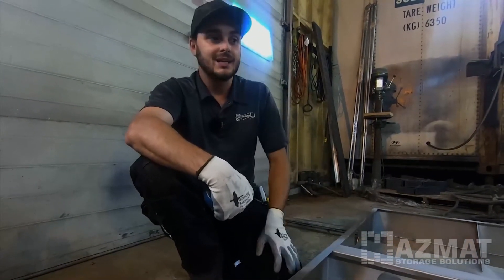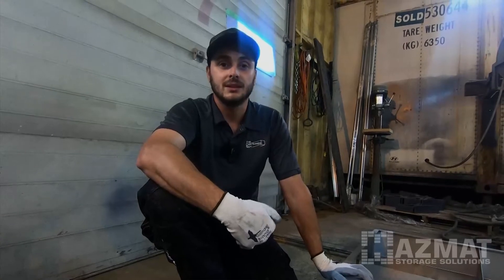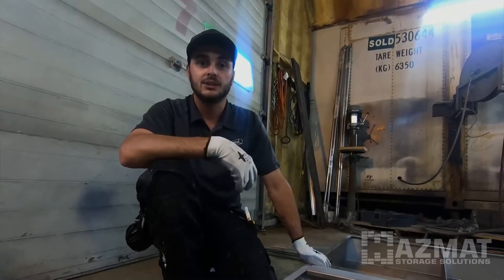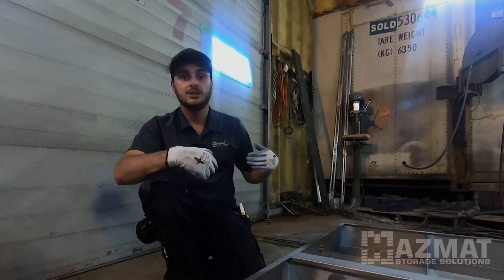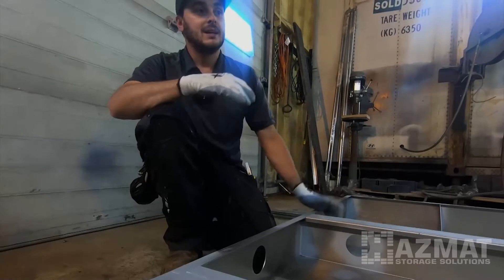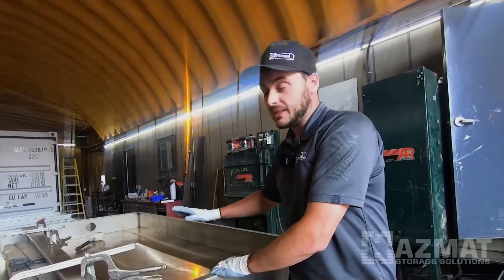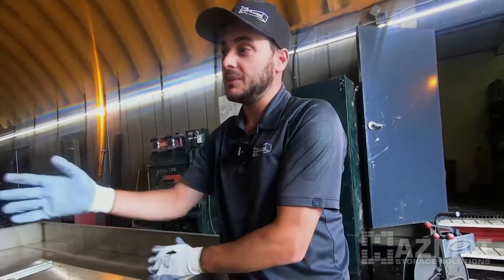This one we've chosen 6 inches of depth, which provides 2,000 litres or 530 US gallons. We'll be able to store about 90% of that inside the container. It's often wise to label your total capacity on the side of the container so people operating this HAZMAT building know their limit. If you already own a container and just need secondary containment, we can pre-manufacture and ship out the pans. What's neat is we can stack the pans with the bar grating, ship it to a customer, and they can easily connect the three pans with the bulkhead fittings, install the grating, and clip it down. Each containment pan is compartmentalized so a small spill stays in one compartment, and if the volume is large enough it will eventually spill over from compartment to compartment.